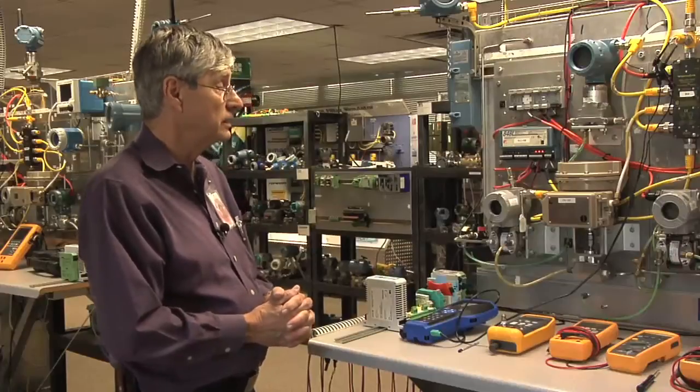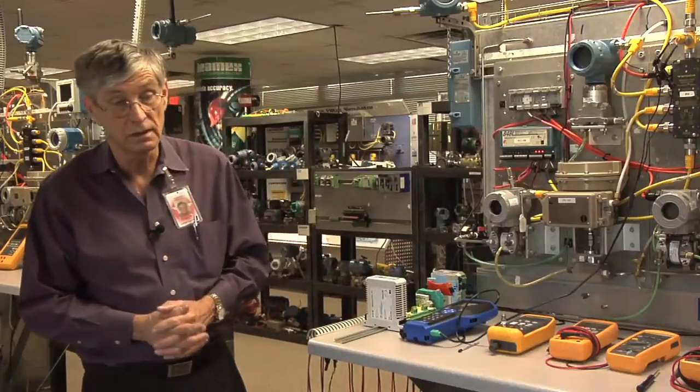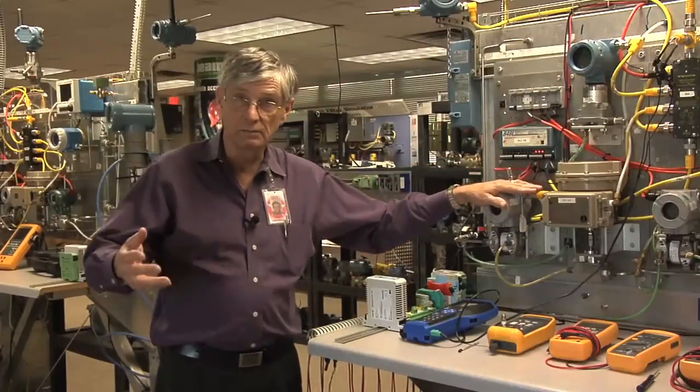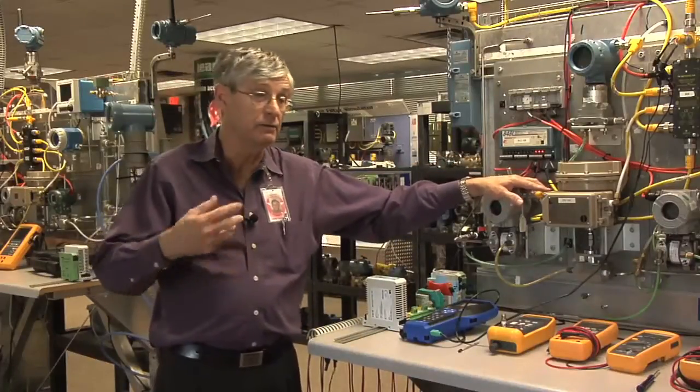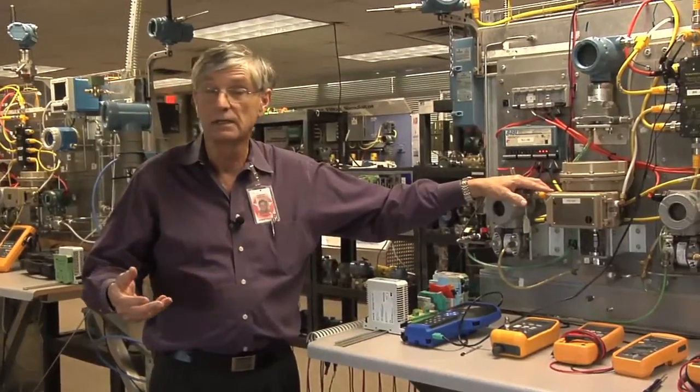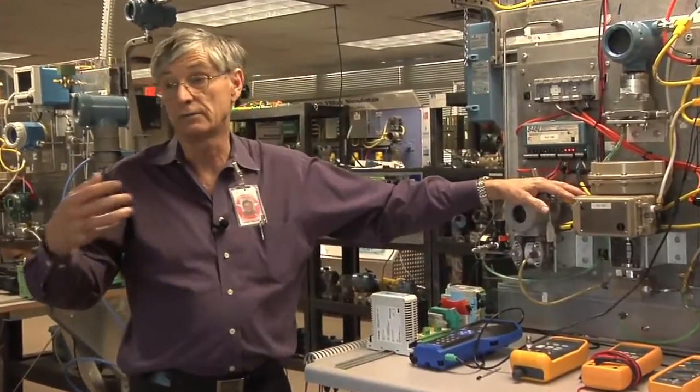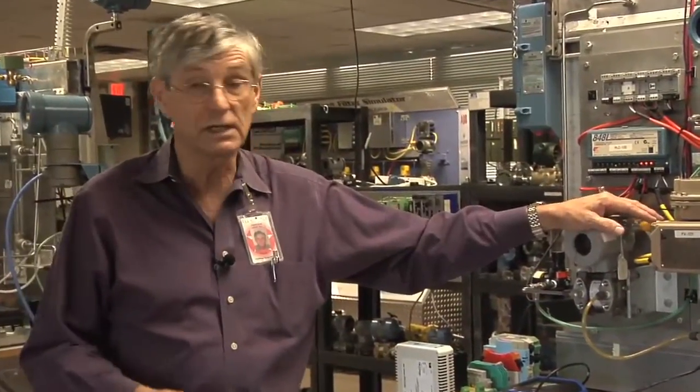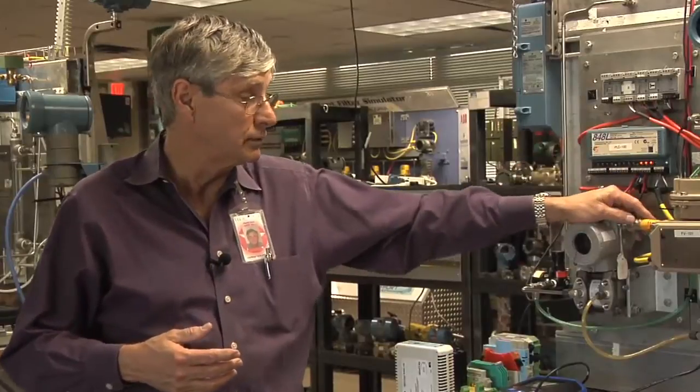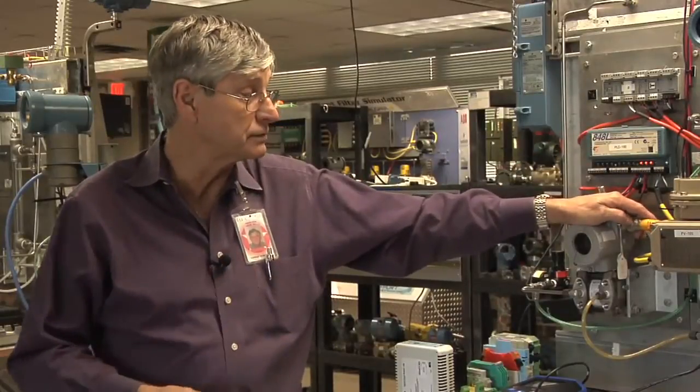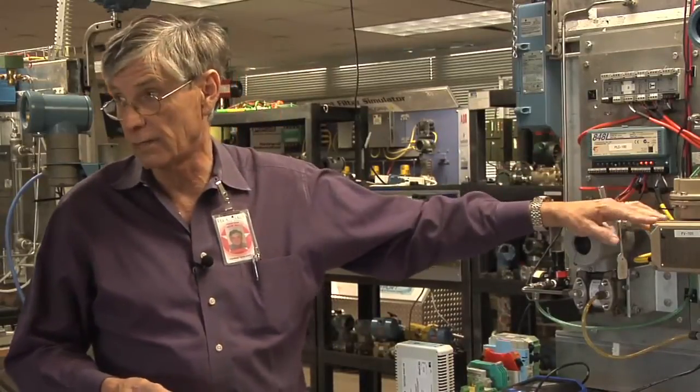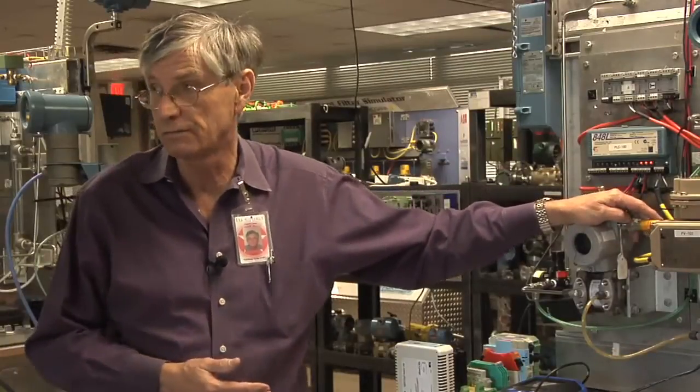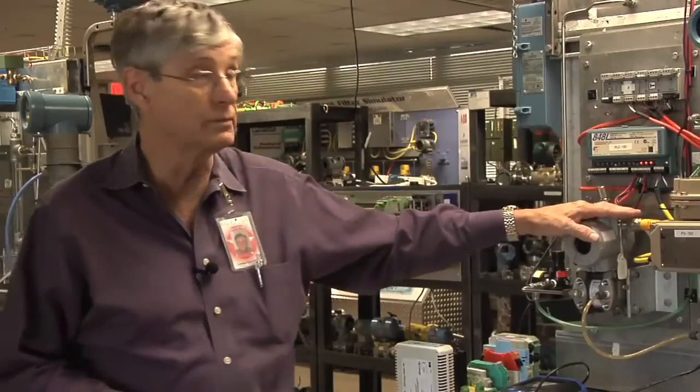And the last thing that we're going to demonstrate is what happens on failure of the measurement coming into the device. In most cases, in a plant, an individual operator would have to recognize that and in some cases may have to go and remove the controller from automatic and place it to manual. In this case, we'll demonstrate that when we remove the device, the measurement device from the system, that the valve will automatically shed itself to manual. That is an out-of-the-box feature with field bus devices and field bus control.